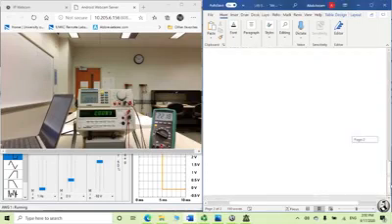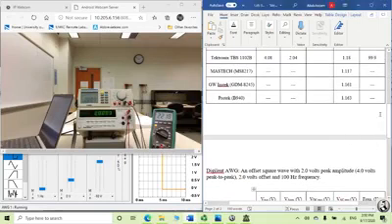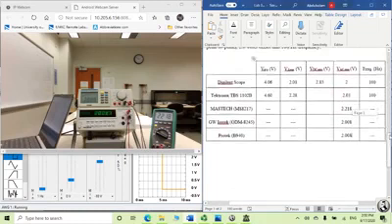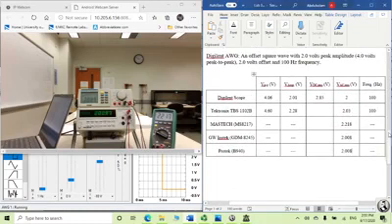Now we are done with these waveforms, but let me check one thing. As you can see in the sheet, Mastech will tell you that some meters are not giving you the right RMS. Why? Because they are only calibrated for sinusoidal waves.